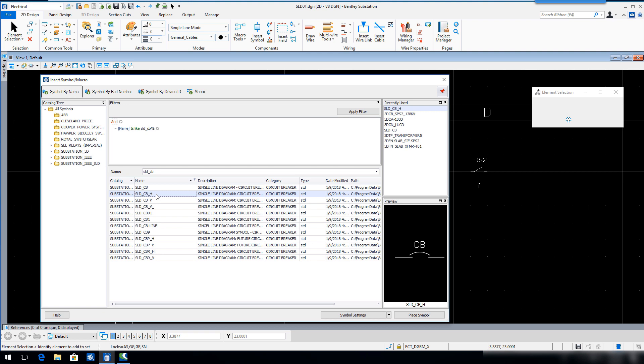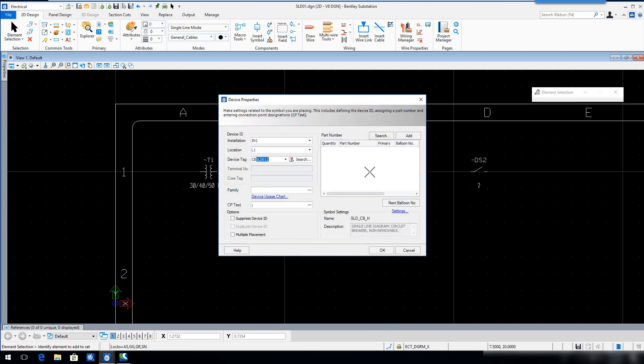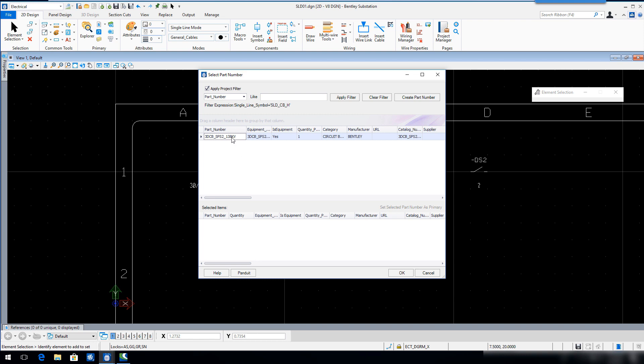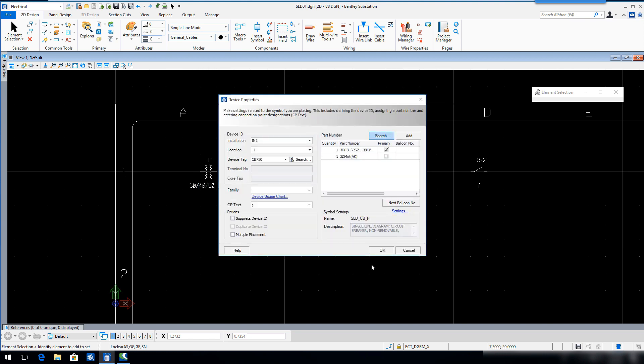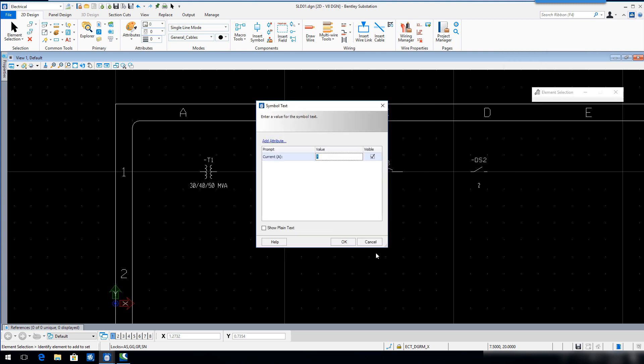Select Place Symbol and insert the circuit breaker symbol in Sector C1 in line with the previously placed symbols. Key in CB730 for the device tag. In the part number area, click the search tool. Double click part number 3DCB underscore SPS2 underscore 138KV and then click OK. Click OK to close the device properties dialog and click OK to accept the default symbol text.